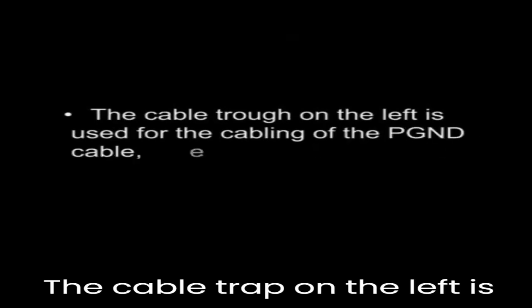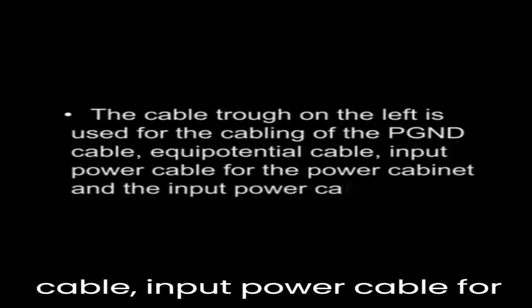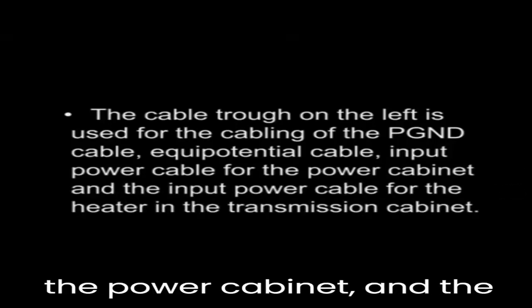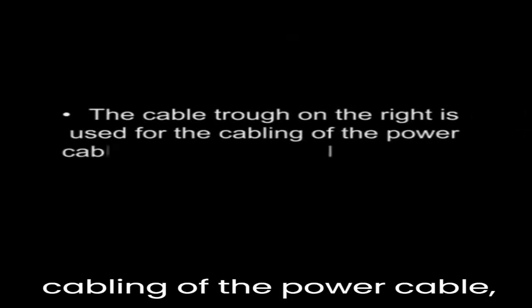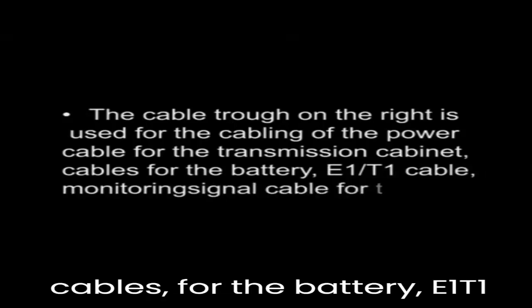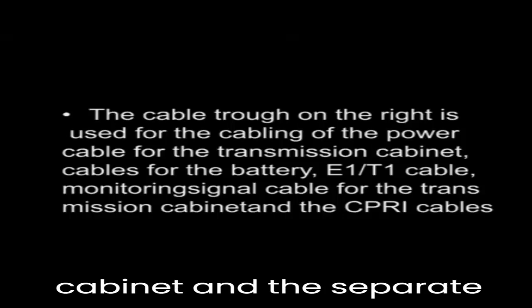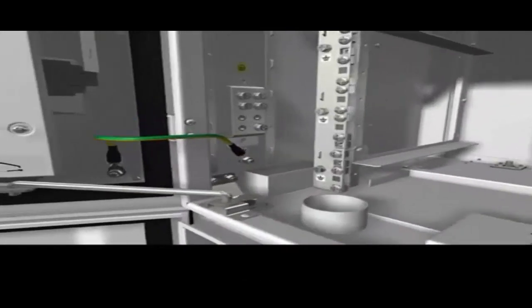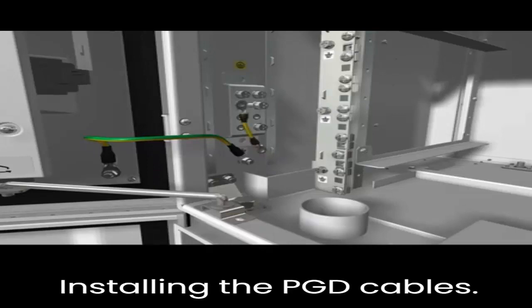The cable trough on the left is used for the cabling of the PGND cable, equipotential cable, input power cable for the power cabinet, and the input power cable for the heater in the transmission cabinet. The cable trough on the right is used for the cabling of the power cable for the transmission cabinet, cables for the battery, E1/T1 cable, monitoring signal cable for the transmission cabinet, and the CPRI cables. Installing the PGND cables.